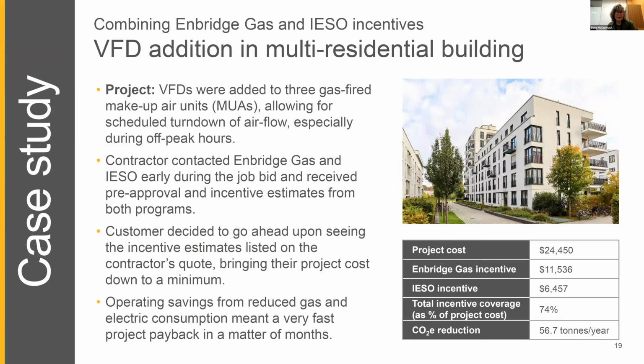I think this is often sort of dismissed as a viable measure that has a big impact. But as you can see, they added VFDs to 3 gas-fired makeup air units. The savings were quite substantial. Project cost was only $24,000 for the 3 units. They exercised applying for all incentives possible, so Enbridge and IESO, and 74% of the total project was covered. You can see there was a significant reduction in CO2. There's very low disruption to the tenants, which is always important. The work is all done on the rooftop, and it was just an overall win for the customer.